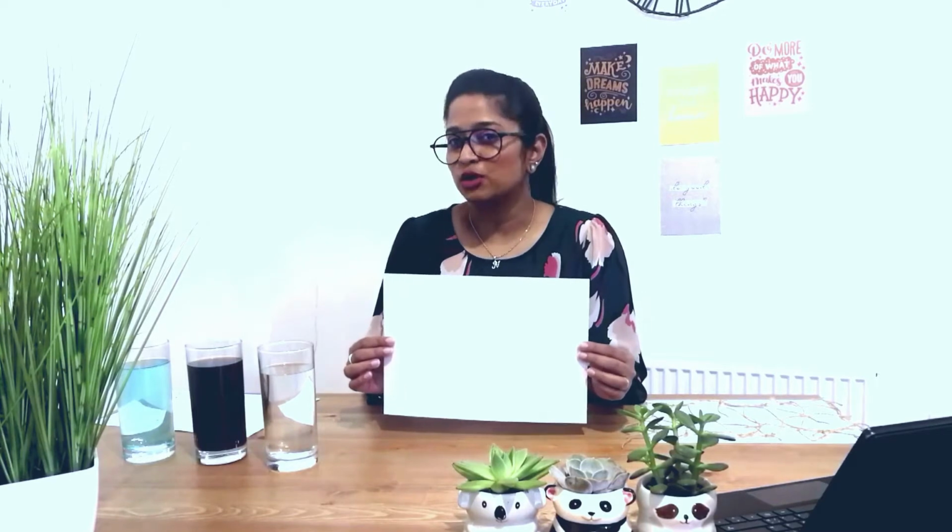A flat sheet membrane would look something like this piece of paper, and it would contain millions of small pores that are invisible to the naked eye. At a large scale membrane facility, we use many such large sheets of membrane that are stacked up against one another, and they're kept apart by something called a spacer. A spacer is typically made of plastic, and its structure would resemble something of a fishing net.